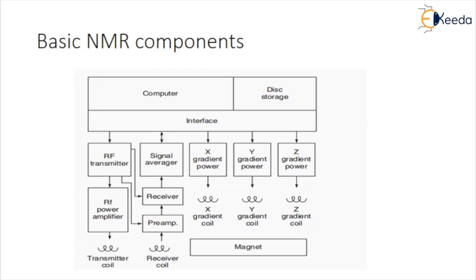RF transmitter system: in order to activate the nuclei so that they emit a useful signal, energy must be transmitted into the sample — this is what the transmitter does. The system consists of an RF transmitter, RF power amplifier, and RF transmitting coils. The RF transmitter consists of an RF crystal oscillator at the Larmor frequency.